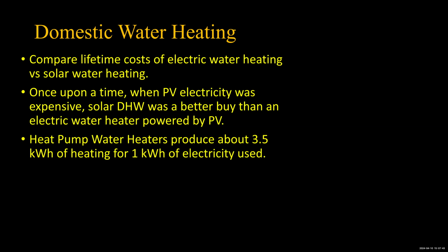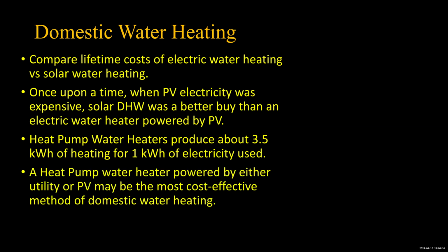So they extract heat from the local environment and dump it into the water. And of course, when you take heat out of the environment local to the water heater, what happens to that local environment? Well, it cools down. So you get a secondary benefit if you want that space, which if it's a garage, you probably do want it cooled off a little bit. So in any case, you've got 3.5 kilowatt hours of heating for every kilowatt hour of electricity you use. Not a bad deal. They're a little slower.